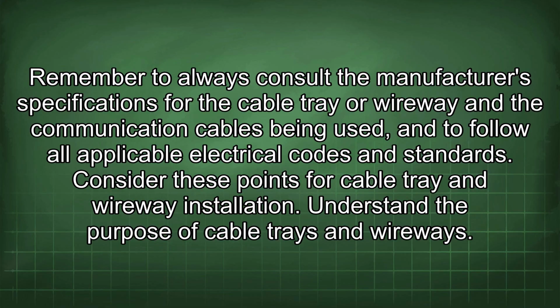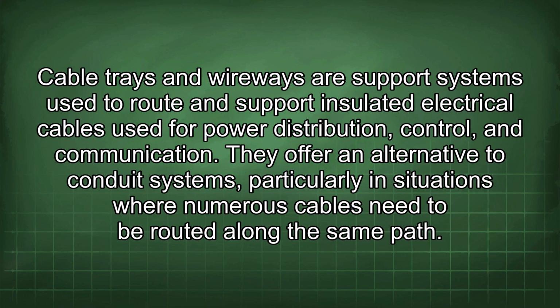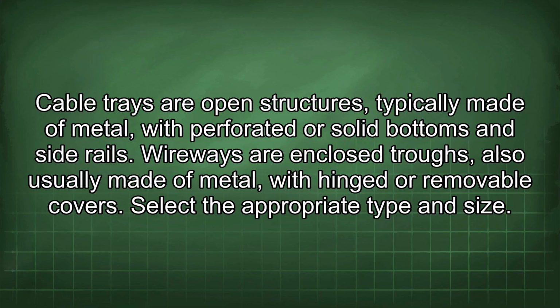Understand the purpose of cable trays and wireways. Cable trays and wireways are support systems used to route and support insulated electrical cables used for power distribution, control, and communication. They offer an alternative to conduit systems, particularly in situations where numerous cables need to be routed along the same path. Cable trays are open structures typically made of metal with perforated or solid bottoms and side rails. Wireways are enclosed troughs, also usually made of metal, with hinged or removable covers.